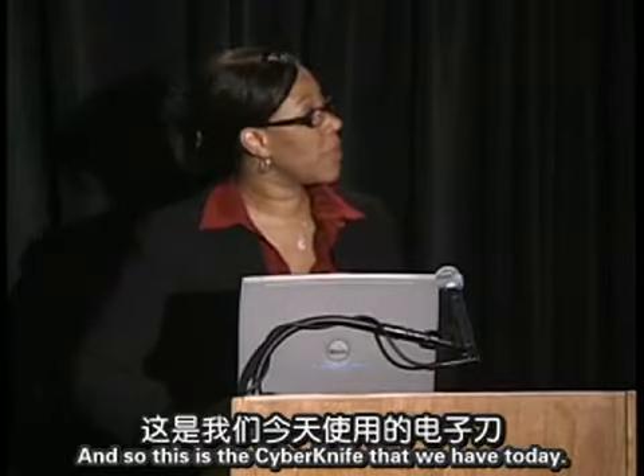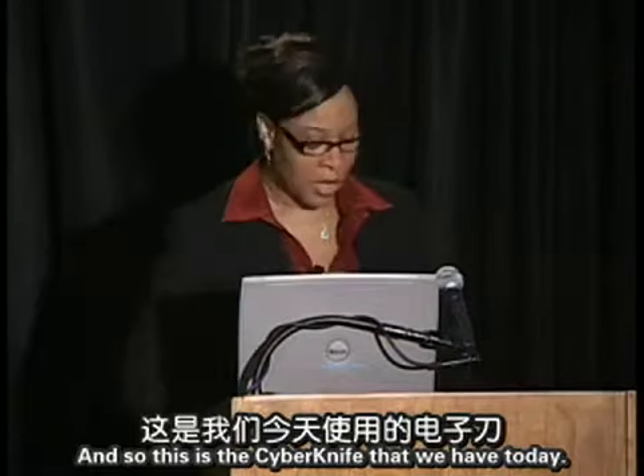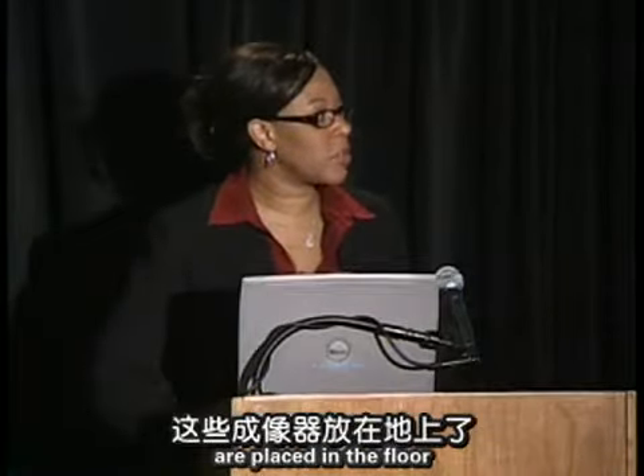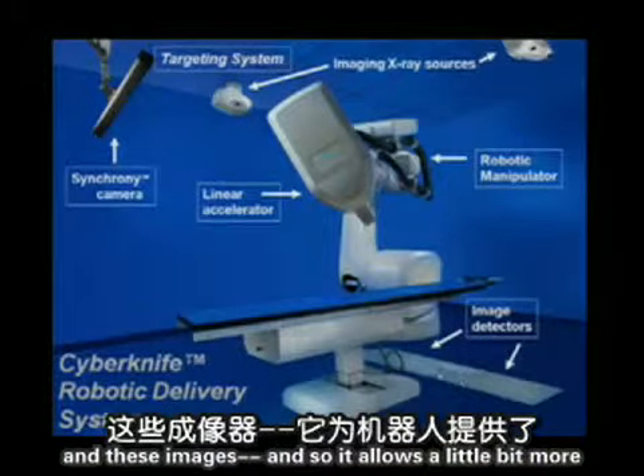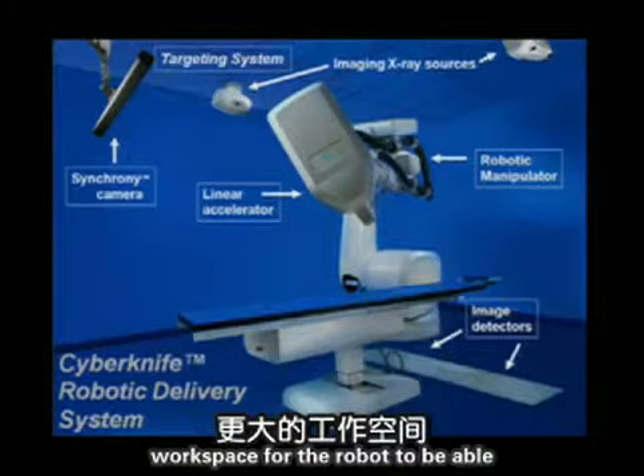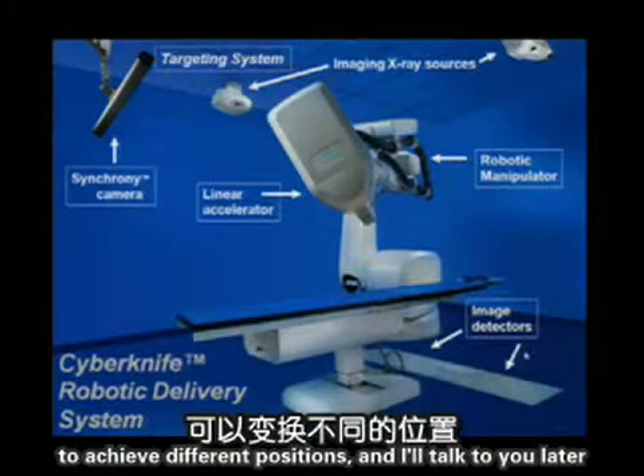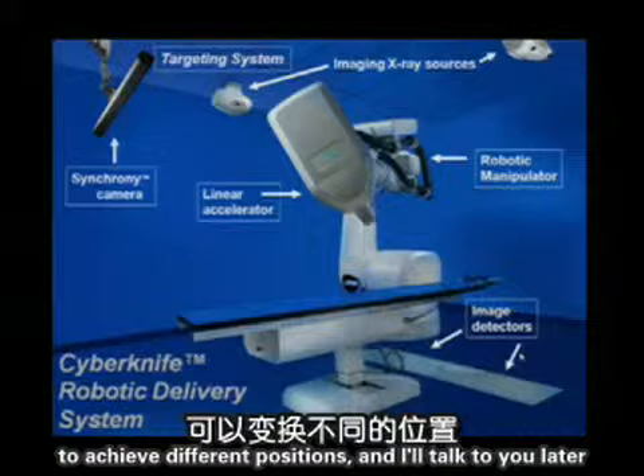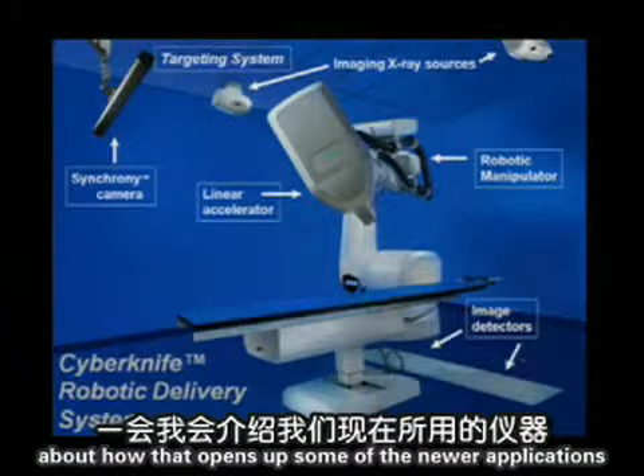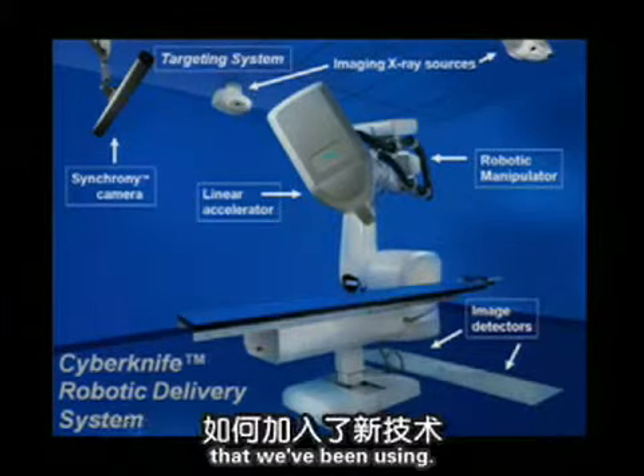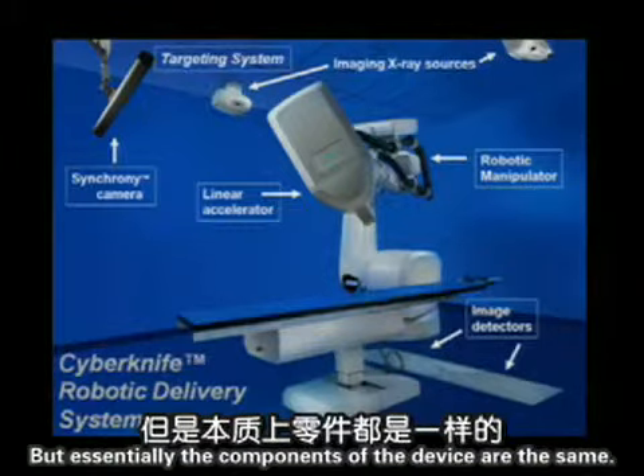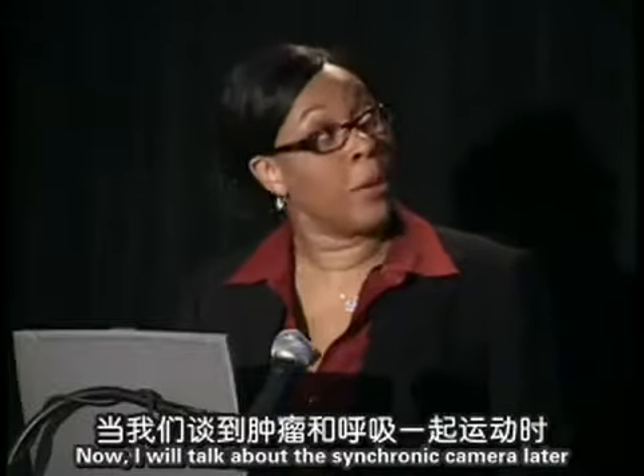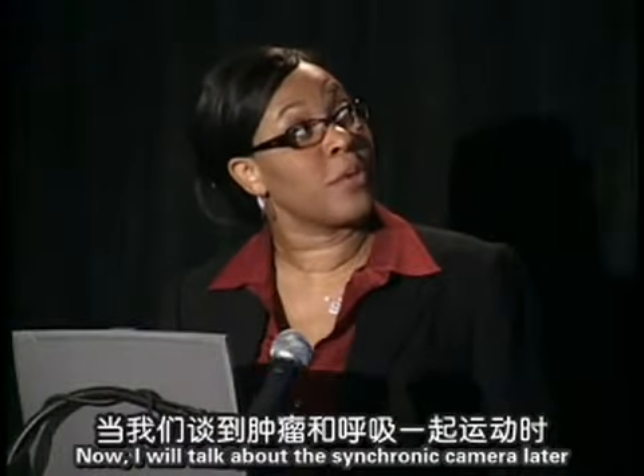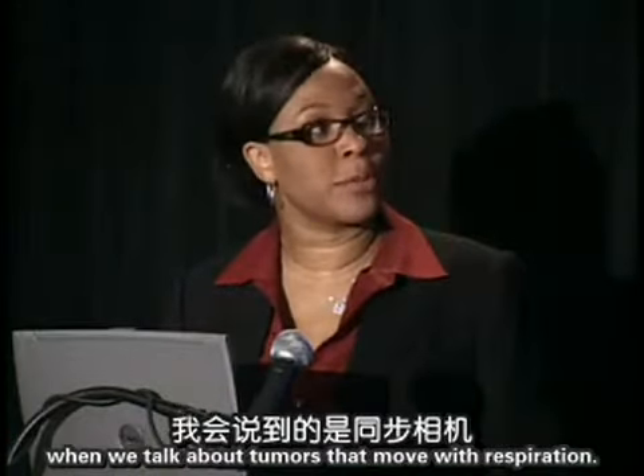And so this is the CyberKnife that we have today. The main changes are that the imagers are placed in the floor, which allows a little bit more workspace for the robot to be able to achieve different positions. I'll talk to you later about how that opens up some of the newer applications that we've been using. Essentially, the components of the device are the same. Now, I will talk about the Synchrony camera later when we talk about tumors that move with respiration.